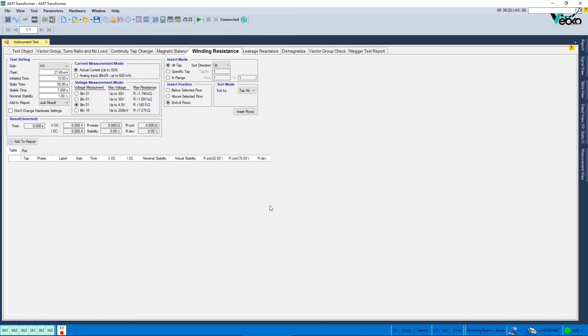If the resistance is bigger than the specified range, the device shows an overvoltage error, in which case you need to either decrease the current or increase the resistance measurement range. Also, if you're facing an error in the current outputs, you need to decrease the current. The order and the position of the taps of the transformers are specified in the Insert Mode and Insert Position section. The mentioned section has already been explained in the video related to the test.